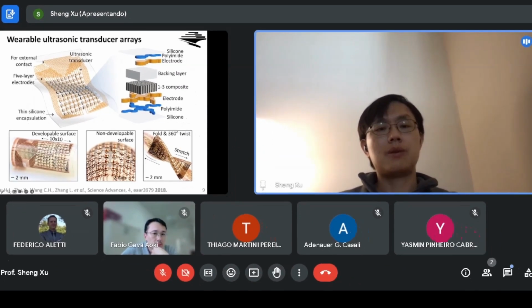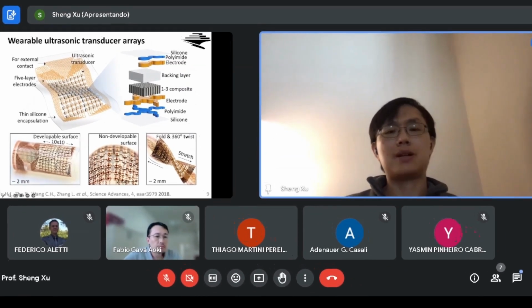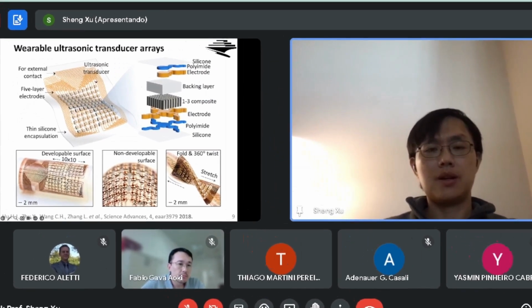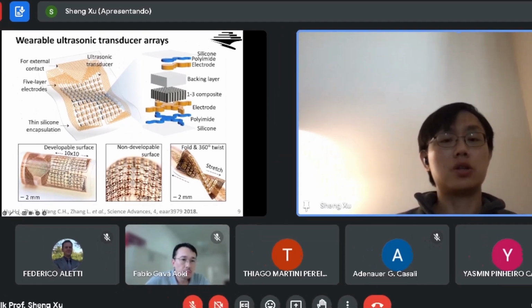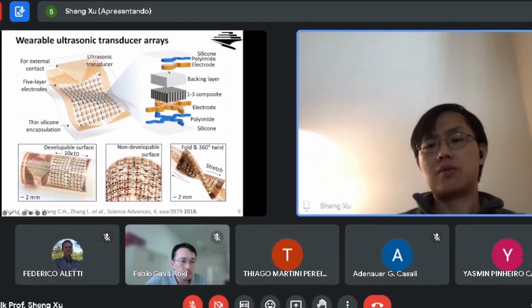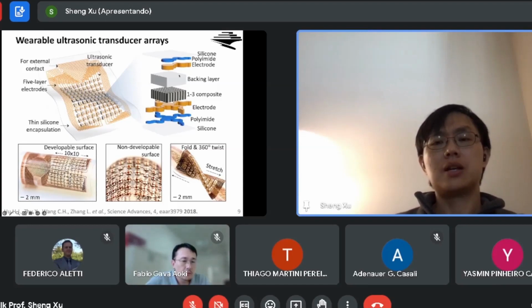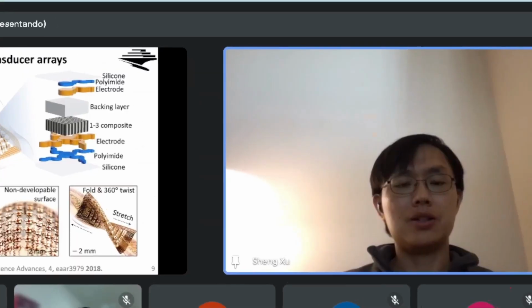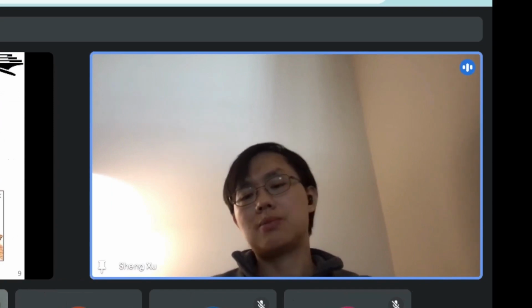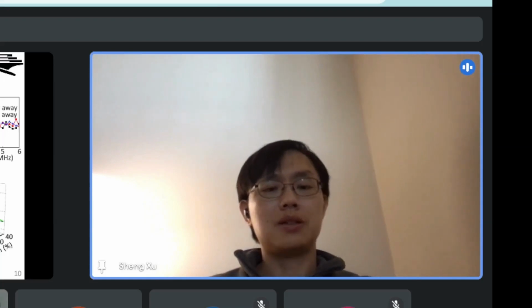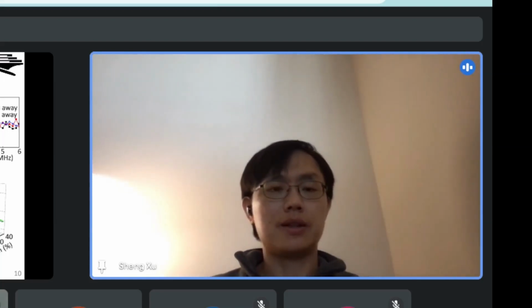So in this wearable ultrasound patch, there are like 100 transducers, a 10 by 10 array. And each one of them is individually controlled to transmit and receive ultrasound. And these are multi-layered, as shown in this exploded view of the device. And those images at the bottom show how soft this wearable ultrasound patch is. It's flexible, stretchable, and it can be twisted, showing the mechanical reliability of this device. So what's the fundamental performance of this ultrasound device?